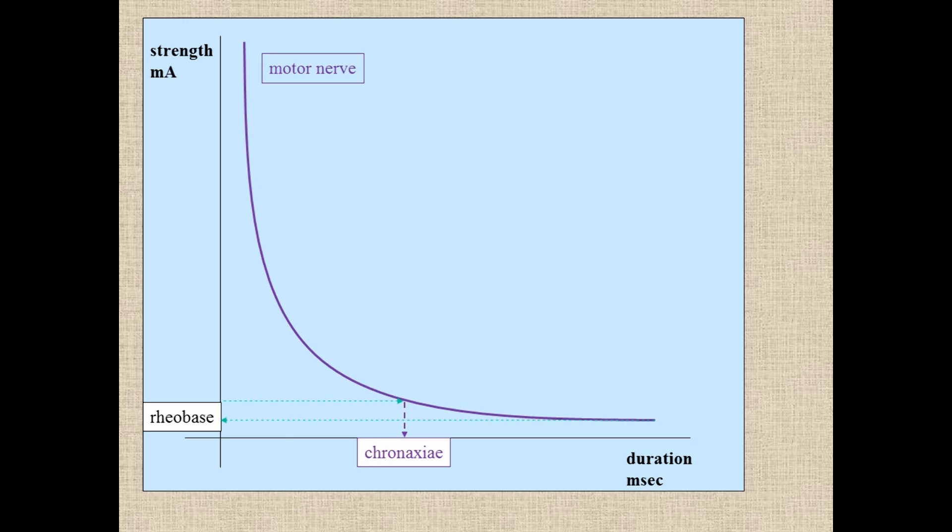So for any nerve system, the ideal place to be stimulating it at is at the chronaxie in terms of impulse duration. Which is why, in mammalian systems with motor nerves, it's about a tenth of a millisecond. I mean, the physiologists have known this for a long time and that's why when they design nerve stimulators, they set them up to work with an impulse duration of about 0.1 of a millisecond. So, in terms of Physiology 101, if you can reproduce that graph in an exam, you can explain how a nerve stimulator works.